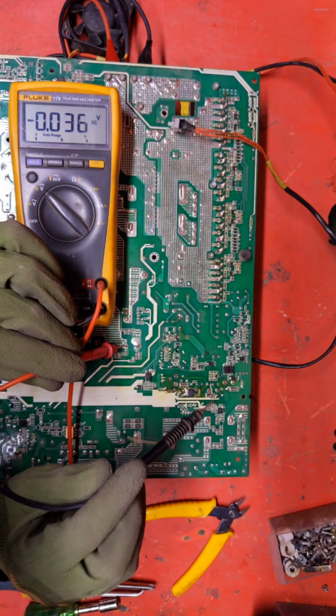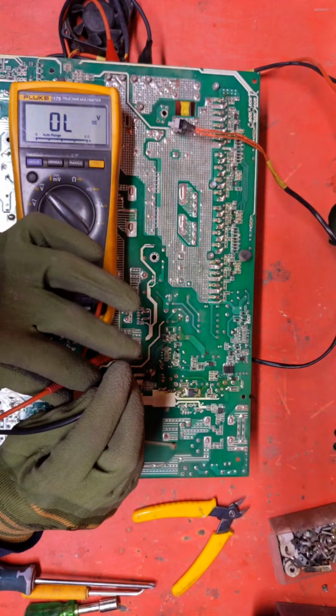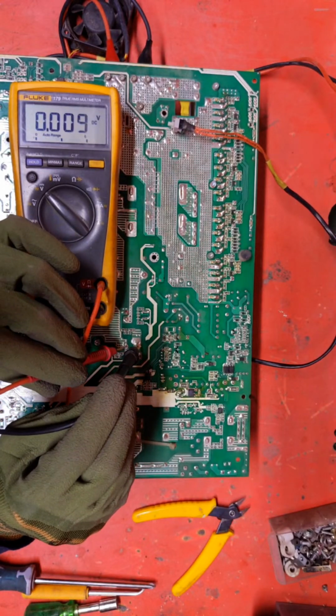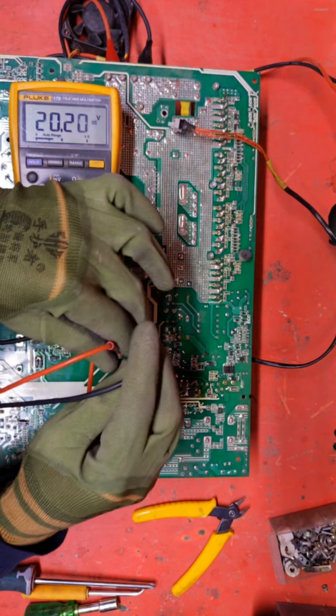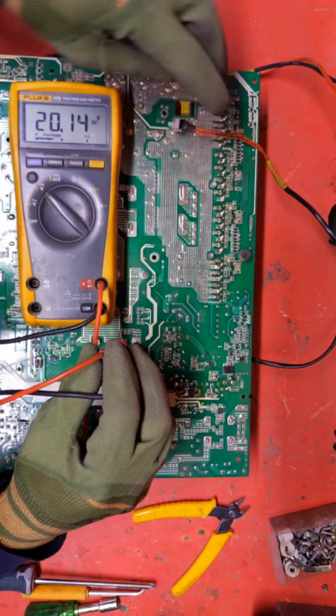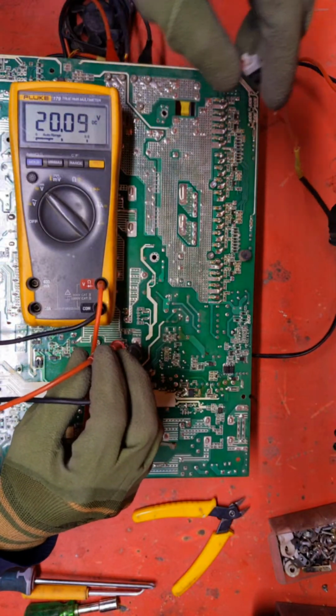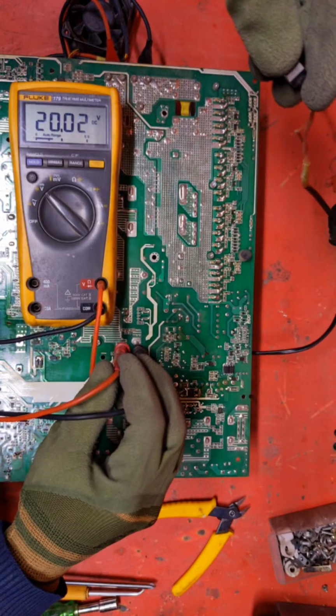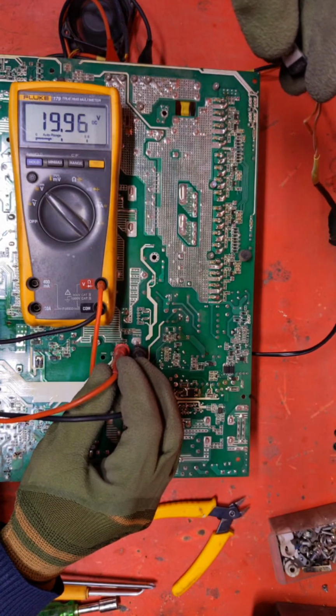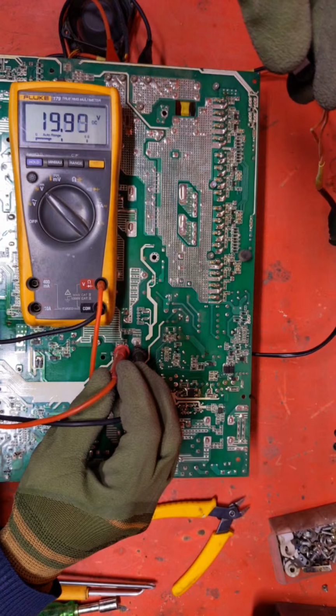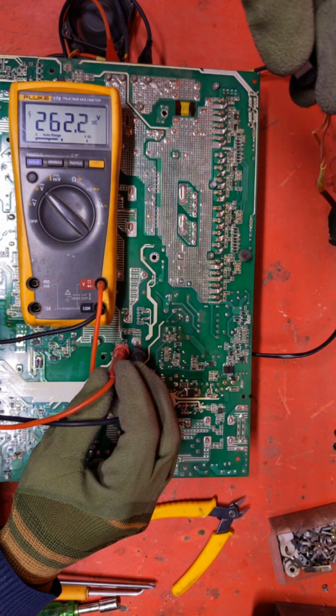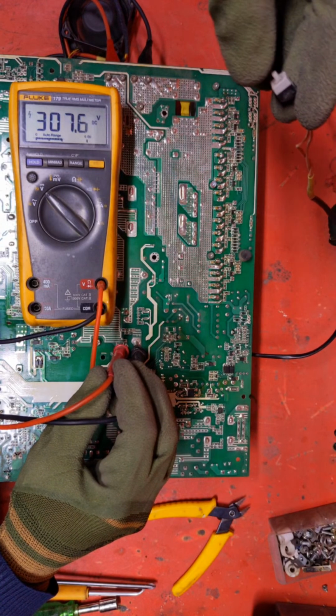Now I need to keep the probes with true continuity, and after that I need to turn on the inverter and check the voltages here. Let's check the soft start voltages. First we need to have this - this is the soft start voltage.